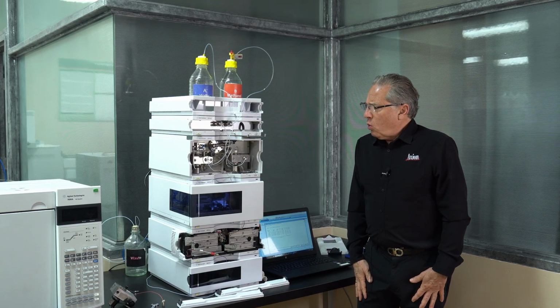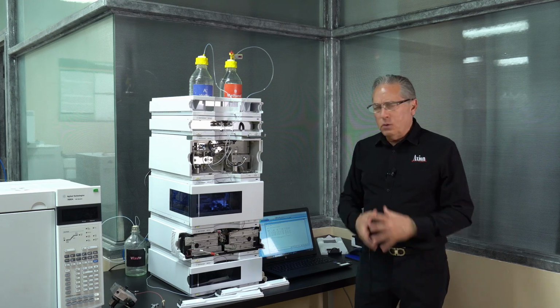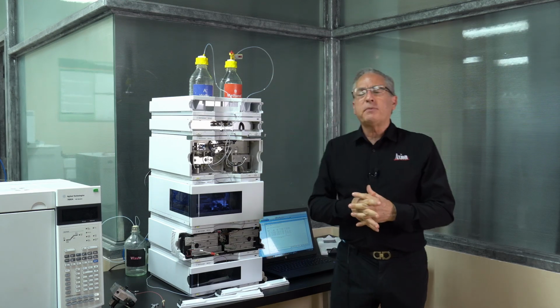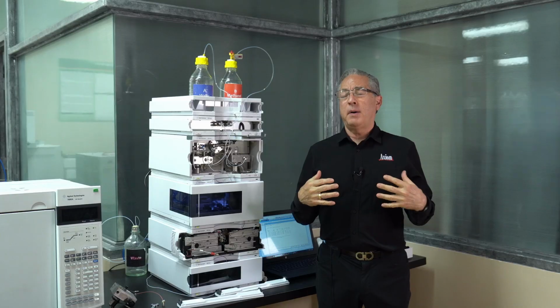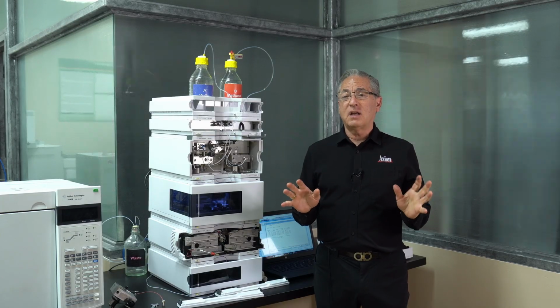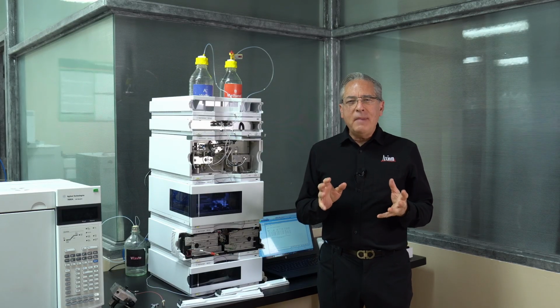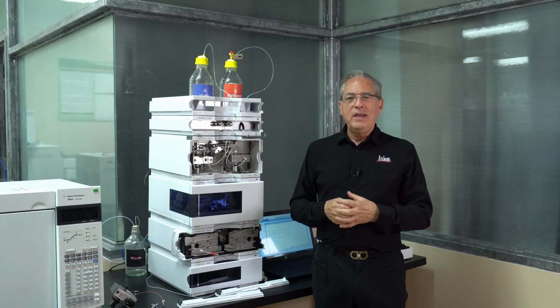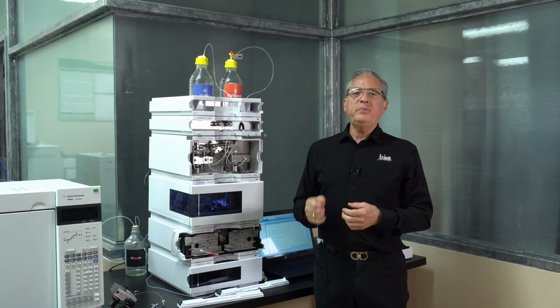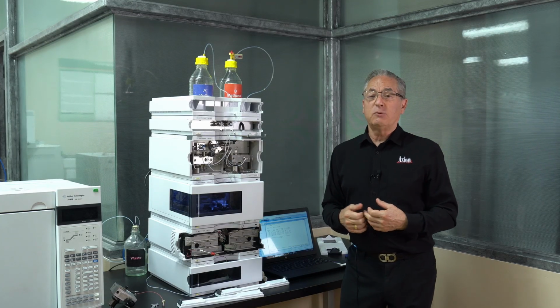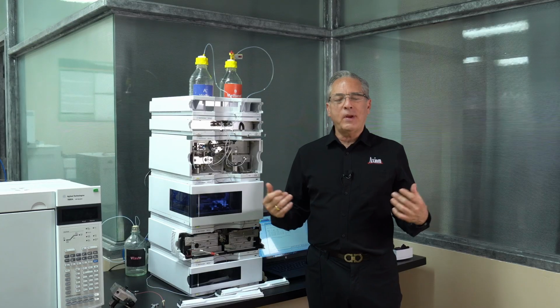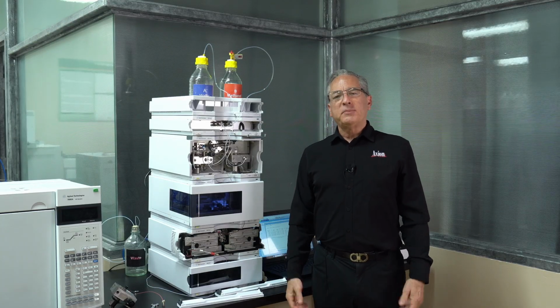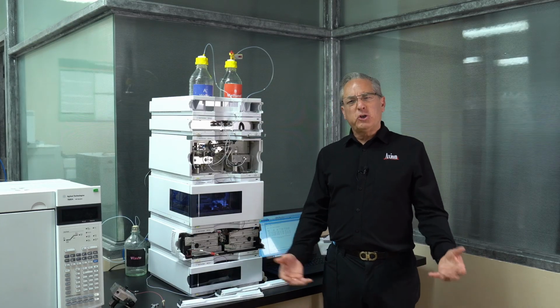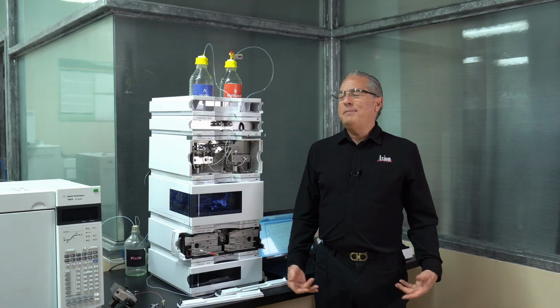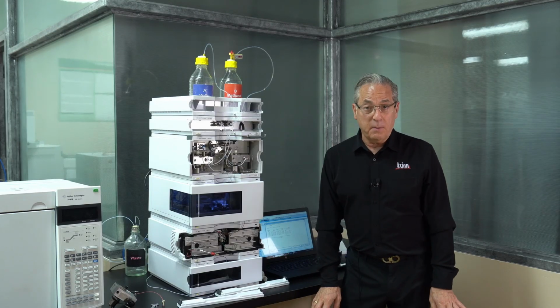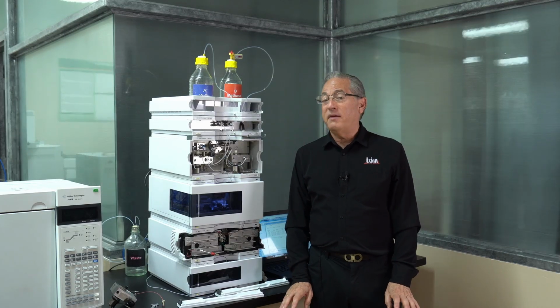Okay, so now I'd like to take you to do some in-depth look at the HPLC pump itself. Remember I said this is where most of your maintenance is going to be, and the primary maintenance task that you're going to do is you're going to change your pump seals. Pump seals need to be changed. I say you change them twice a year. Every 6 months is a great program to get on. How long do pump seals last? We really don't know. It depends what you're doing with them. In my opinion, they easily last a year, but if you change them every 6 months, they'll never wear out.